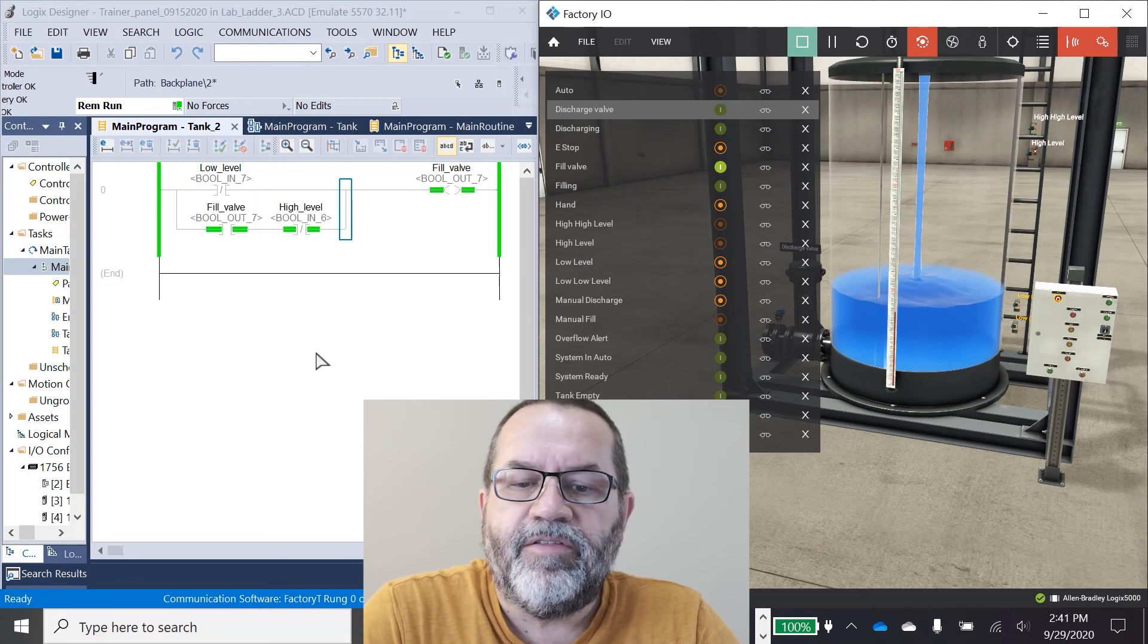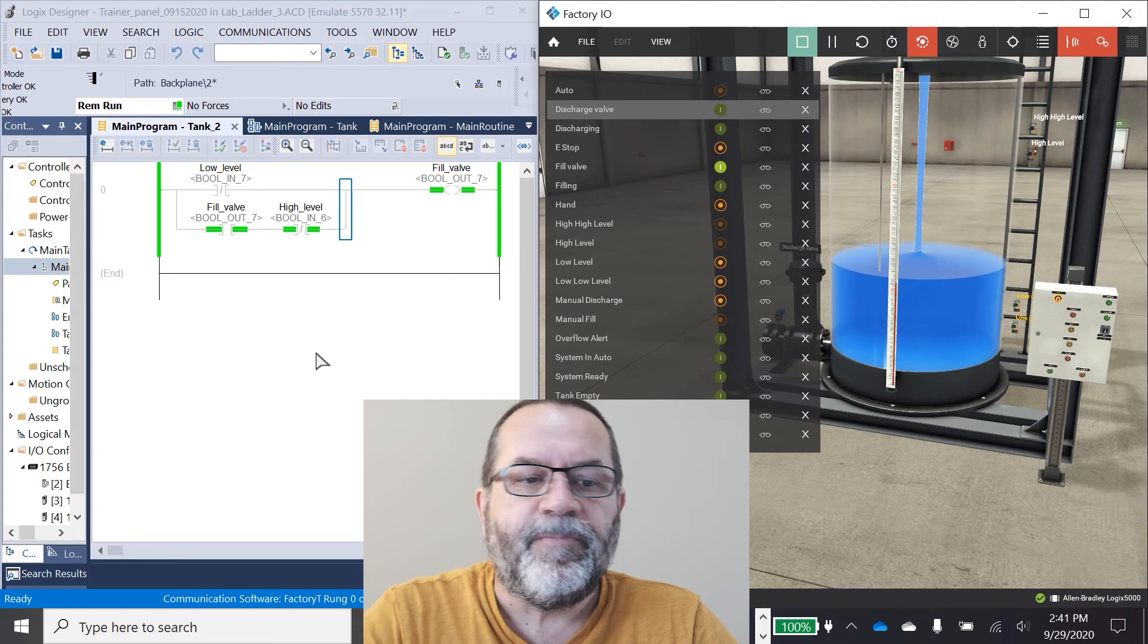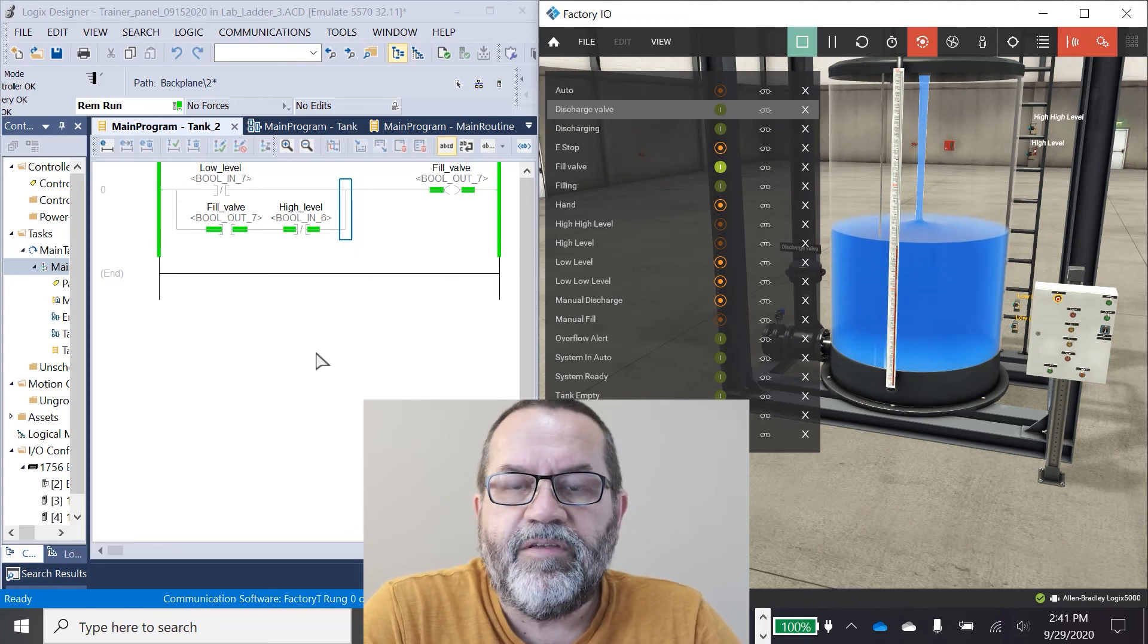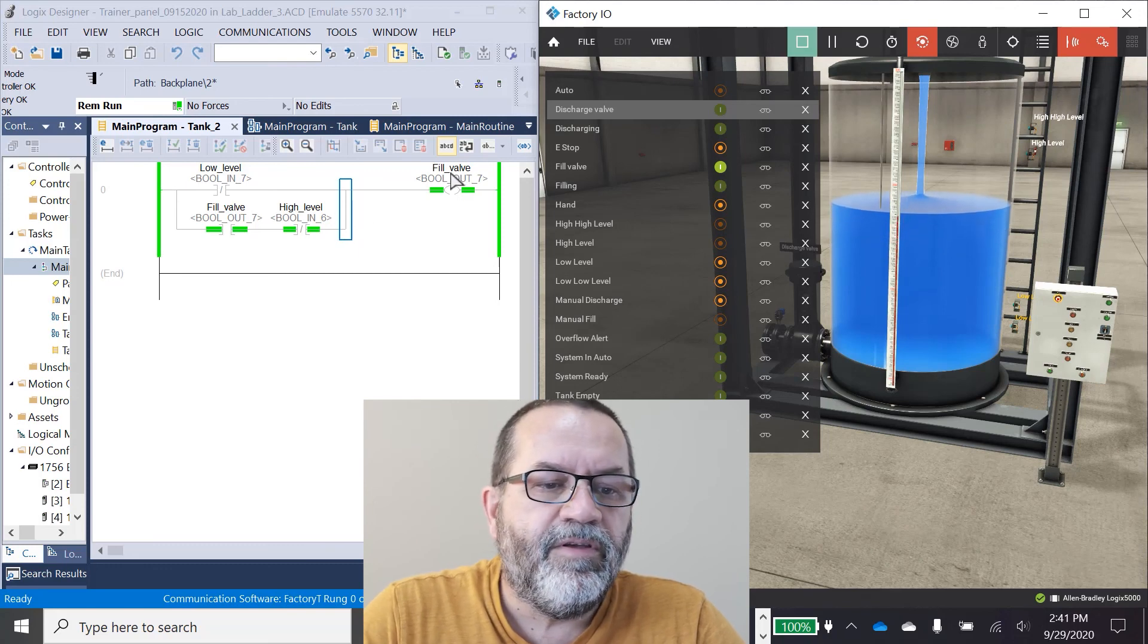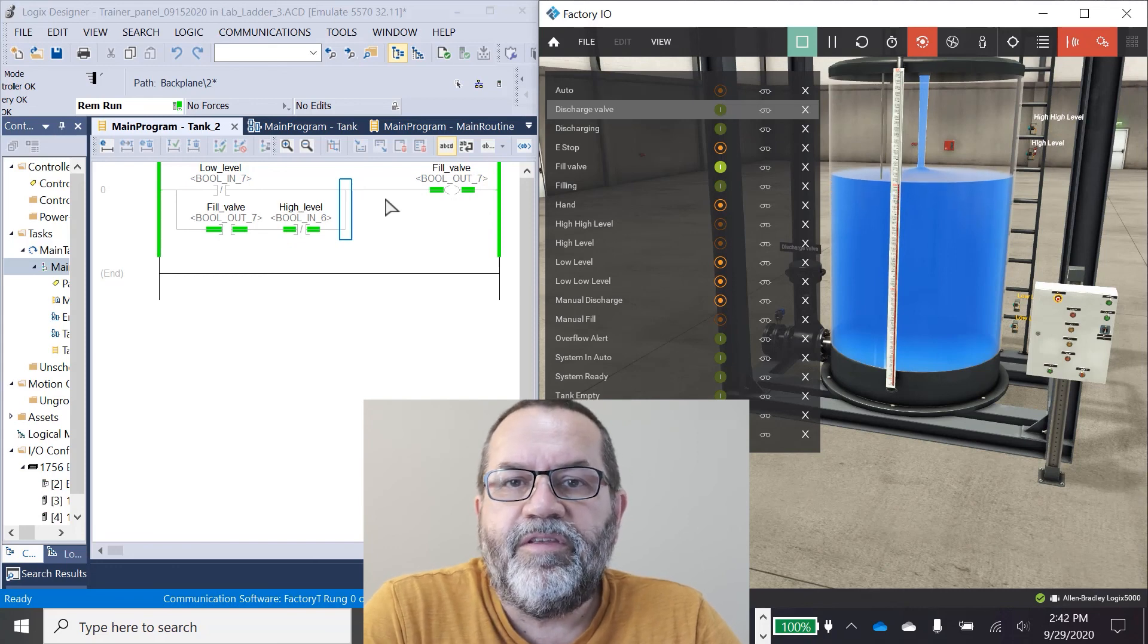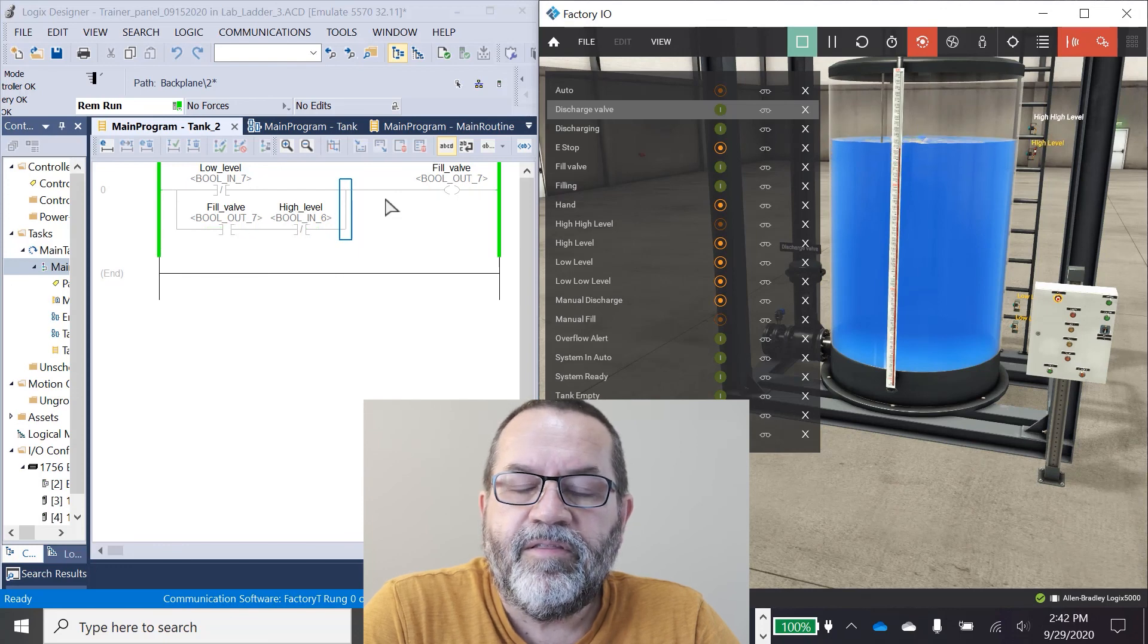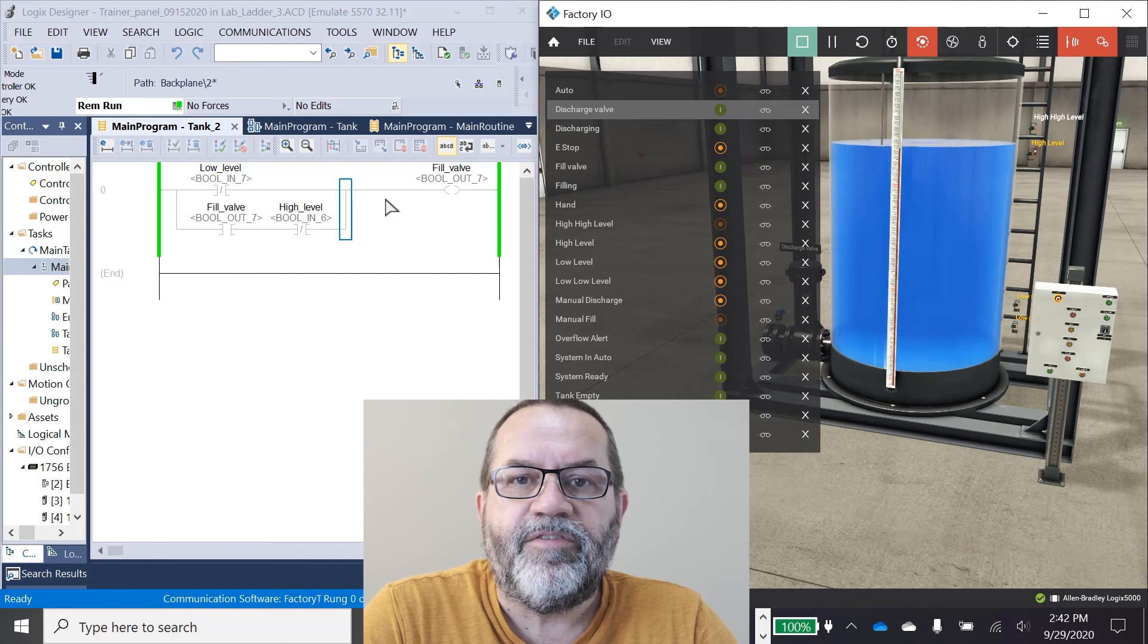Okay, now the cycle starts again and it's going to fill itself up. That's how seal-in logic works. You activate something and you use that thing that you've activated. In this case, it's a fill valve to seal itself on. And then you use something different to break that seal, and the fill stops. Okay, that's how seal-in logic works. Thanks.